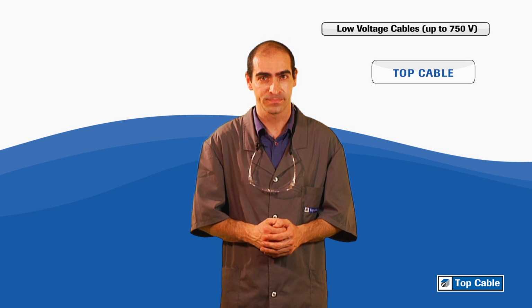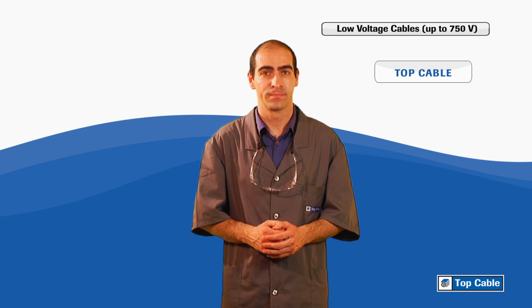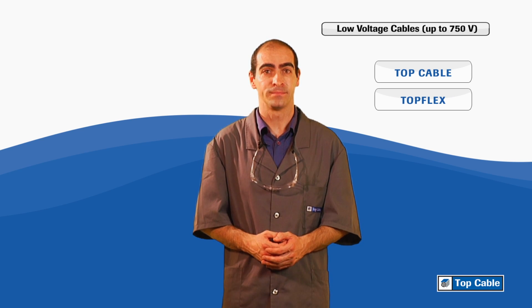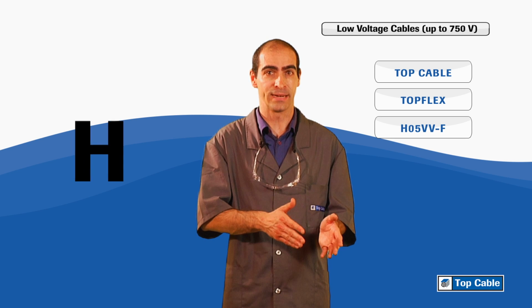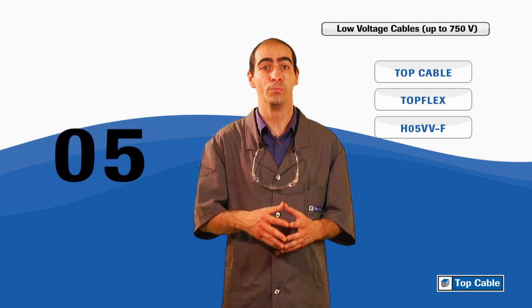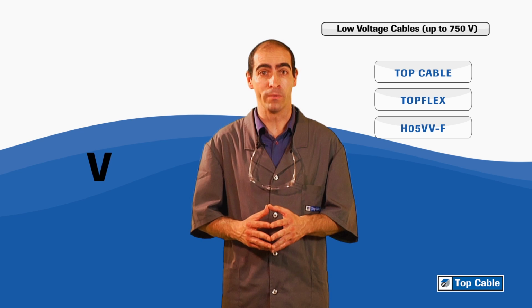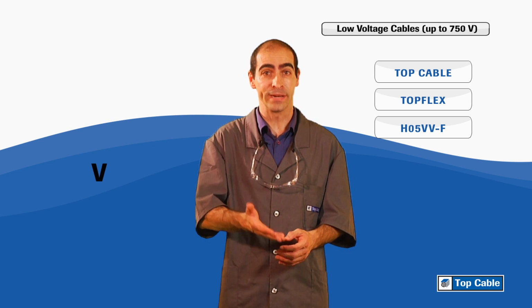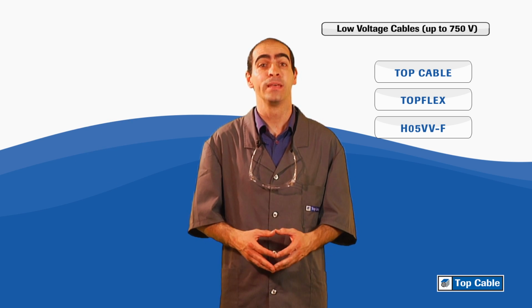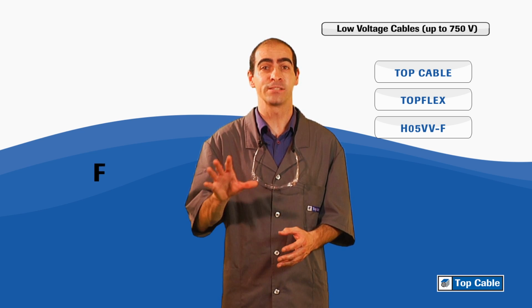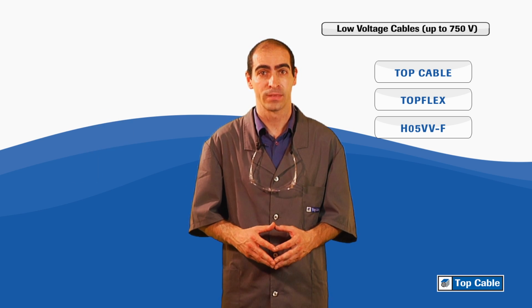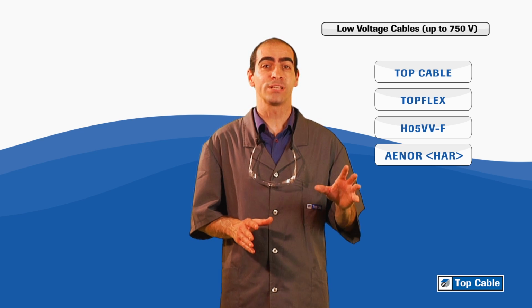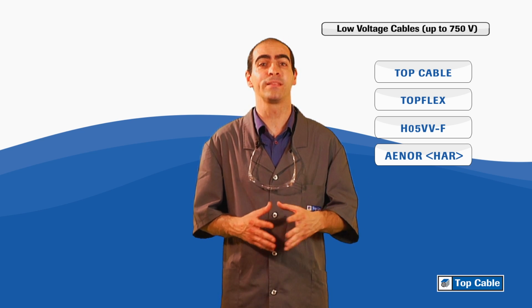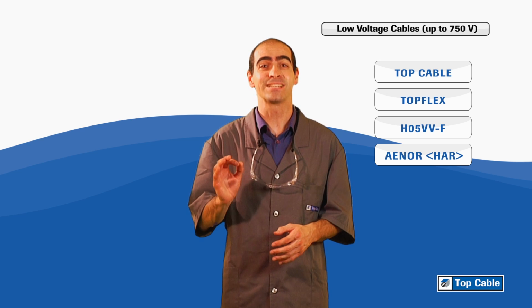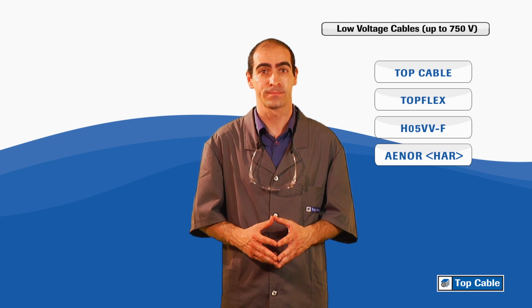Let's see some examples. Cable manufacturer. Trademark of the manufacturer. Harmonized cable, H, of 500 volts, 05. PVC insulation, V. PVC sheath, V. And flexible conductor for mobile services, F. AENOR, HAR, means the product is subject to manufacturing control by an external organization, AENOR, and it is a certified product, HAR.